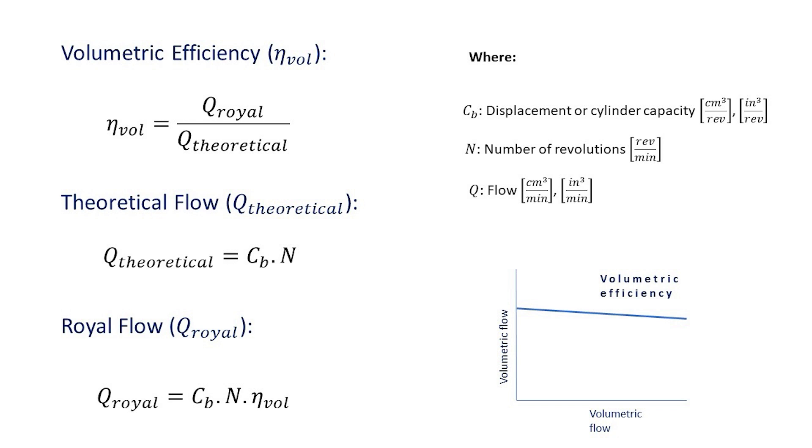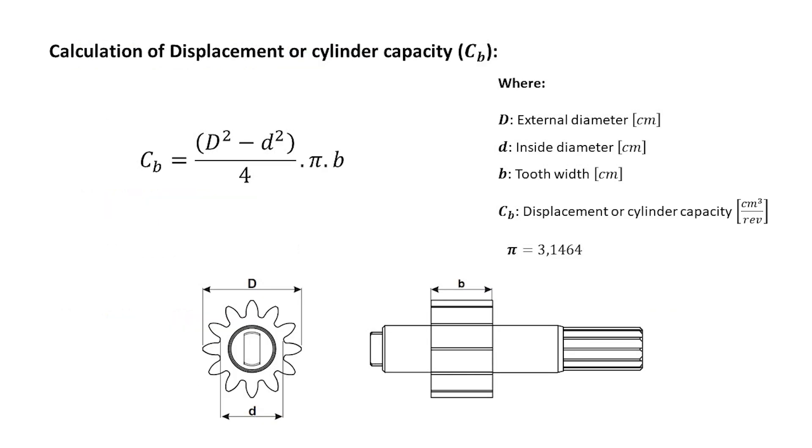The displacement of each pump is specified in its technical sheet, but it can also be calculated. For this type of pumps, the calculation is quite easy. The volumetric displacement is equal to the outer diameter of the gear squared, minus the inner diameter squared, divided by 4, all multiplied by PI, multiplied by the width of the toothing. Remember to replace the data in this formula with the units in centimeters, otherwise you will have to do a unit conversion at the end.